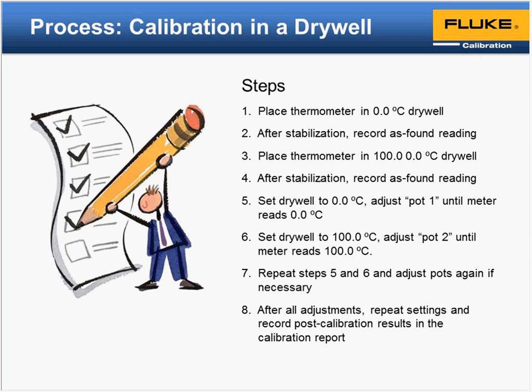A lot of times as you're ramping up and down in temperature, folks will check some midpoint, say a 50 check, or even 75, 50, and 25, just to see where it's pulling out on the tolerance. And again, more data is always better than less. There are some things there, especially if it's costing you time, so again, always a balance. But it's good to get additional data if you're wanting to really see where you're potentially pulling out of that window that you want to be in.